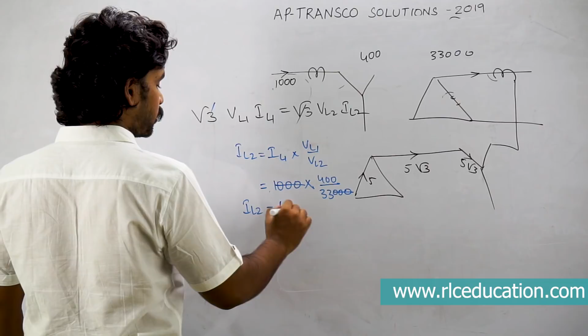So I will find out what the CT ratio is. CT ratio will be the primary side line current, that is 400 by 33, divided by the secondary side phase current, that is 5 root 3. So the 5 and 80s will go. You will get CT ratio as 80 by 33 into root 3. Sir, but the options are not matching. How can we do? We will try to go for a little bit of approximation. So we will approximate by rationalizing the denominator. When you rationalize the denominator, you will get 80 root 3 divided by 33 into 3, that is 99. This will be the final ratio.